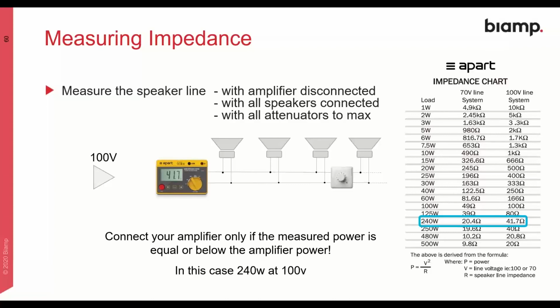So if I look up on the table, which is on the right side, and by the way, this table is supplied with the Impedance, it's in the lid of the Impedance, so you've always got it for reference. I can see here 41.7 ohms at 100 volts. It's looking for an amplifier to drive that of 240 watts. So if your calculations state that you expect only 120 watts, you know something is wrong. Either the tappings haven't been set correctly or loudspeakers haven't been connected correctly. So this is just a safeguard so that when you connect the speaker line to the amplifier, it's not going to be damaged from having too high a load or too low an impedance connected to it, if you like.